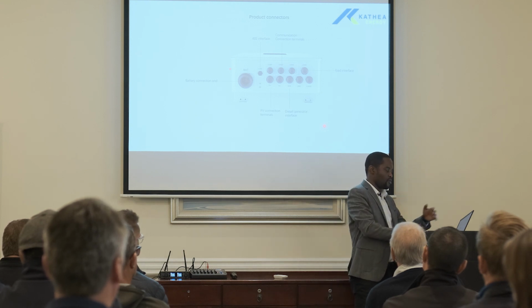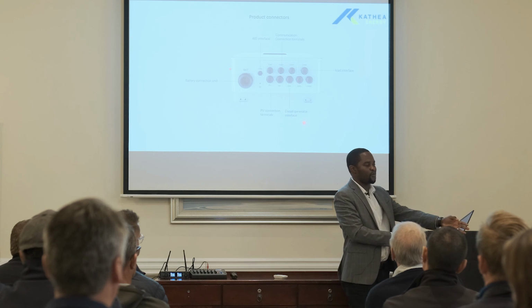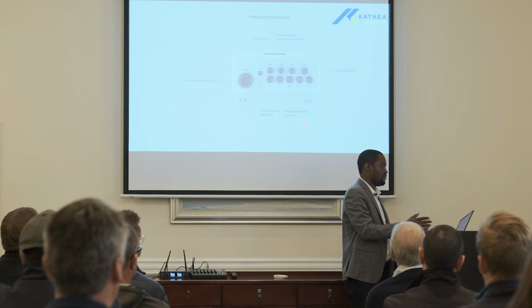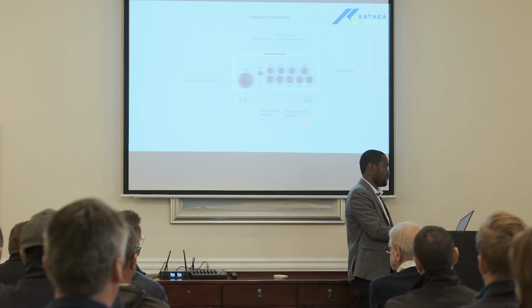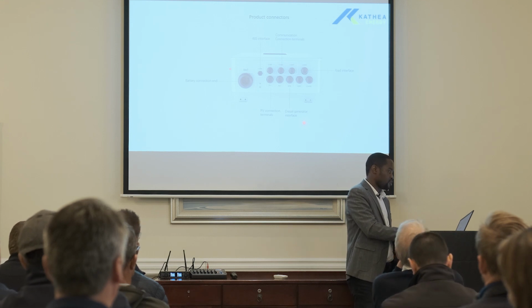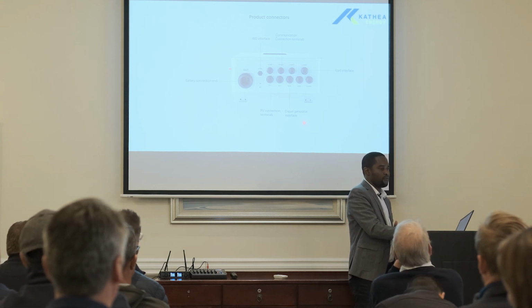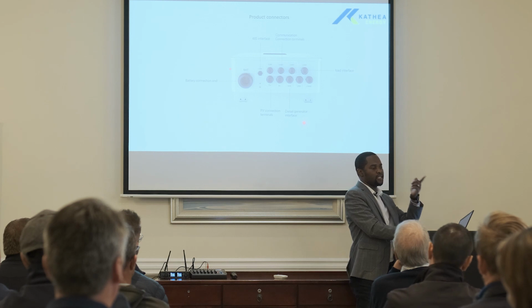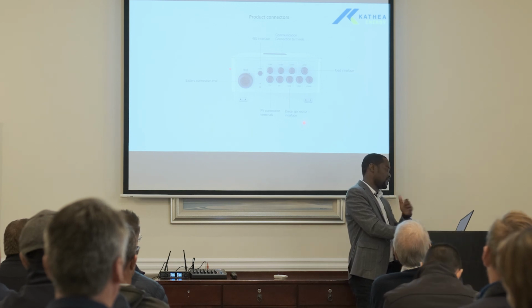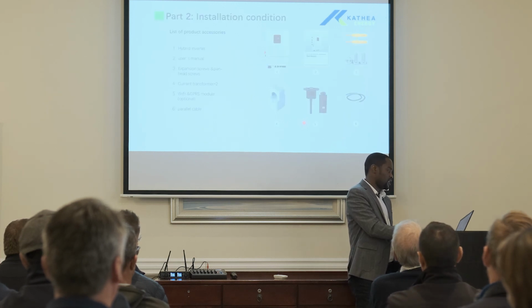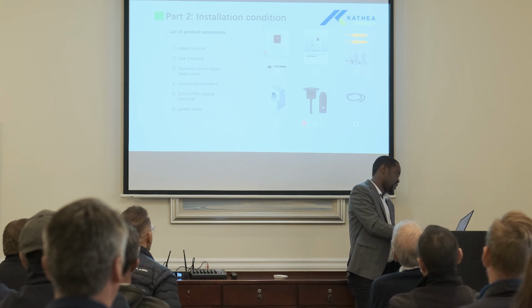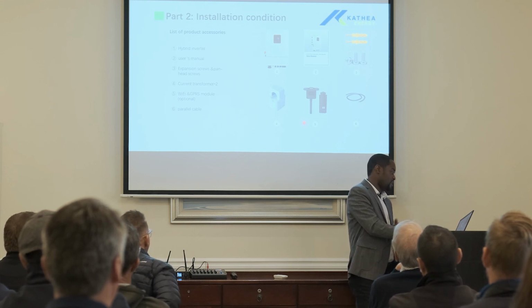So there's no need of really talking about this because it's something that we're going to be able to see. But just giving a background so that when we're seeing or confirming what we've already talked about: the generator, we've got relays on the inverter which can start and stop the generator based on grid availability and the SOC. Just like any other hybrid inverter in that matter, it's not uniquely INVT.